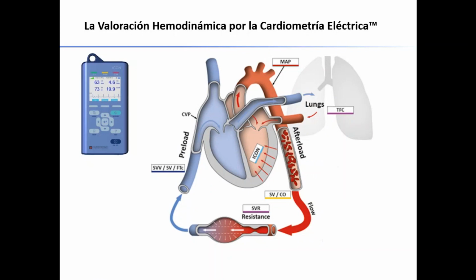Yes, the early studies which we had to present to the US FDA for accepting a market use of a system showed between Swan-Ganz catheter or the PiCCO system, usually correlations in the range of 0.78 and an agreement or an error which was less than about 30%.